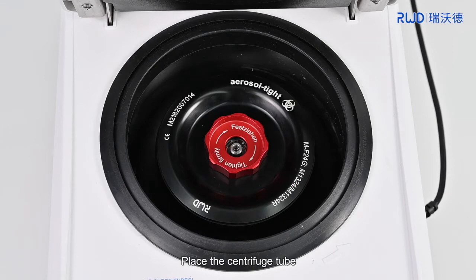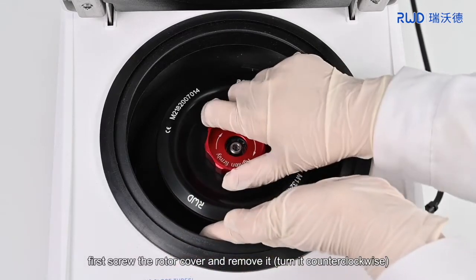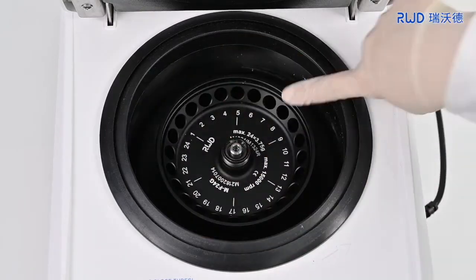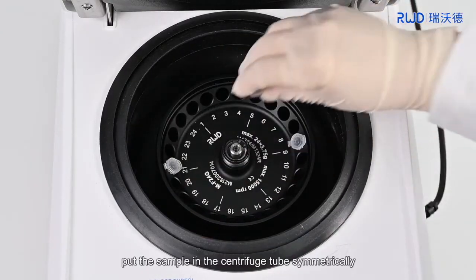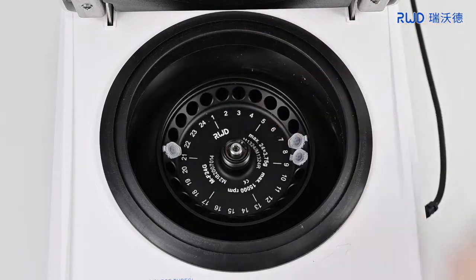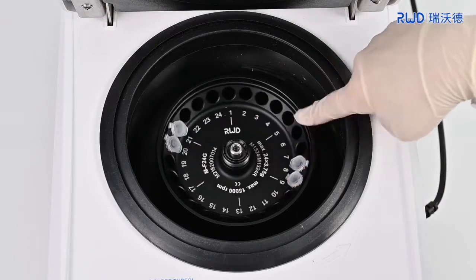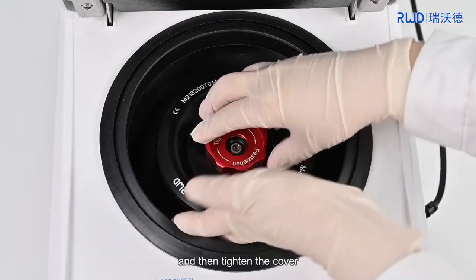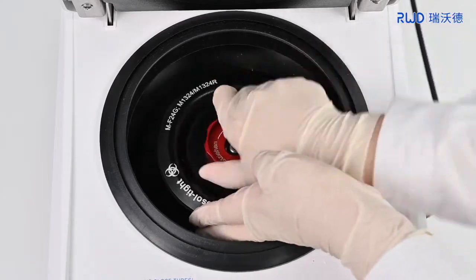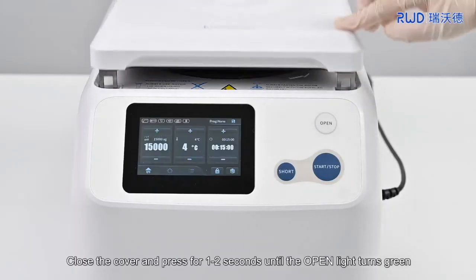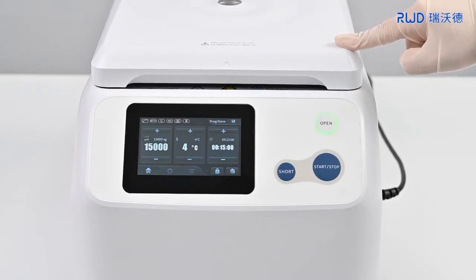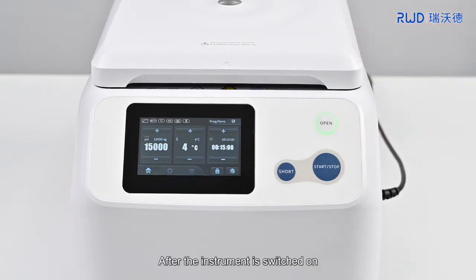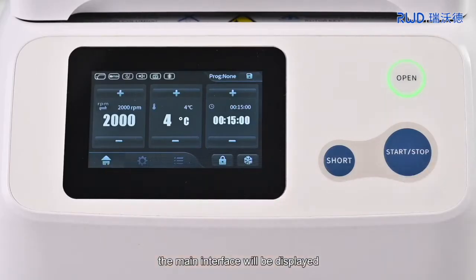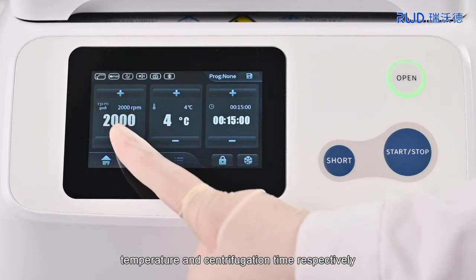Place the centrifuge tube. First unscrew the rotor cover and remove it. Put the sample in the centrifuge tube symmetrically, and then tighten the cover. Close the cover and press for 1 to 2 seconds until the open light turns green. After the instrument is switched on, the main interface will be displayed, including the centrifugation speed or centrifugal force, temperature, and centrifugation time respectively.